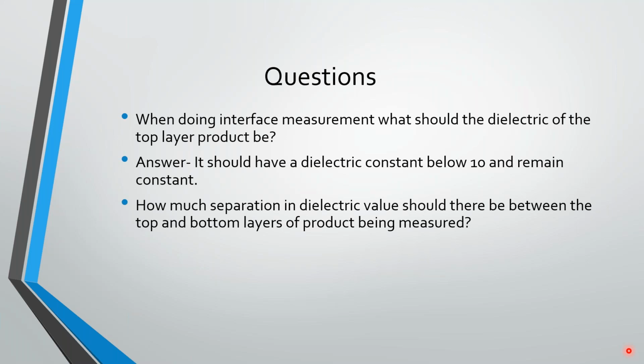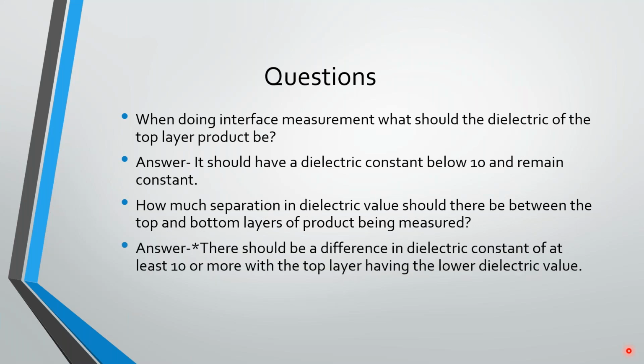How much separation in dielectric value should there be between the top and bottom layers of the products being measured? Again, it's 10 - there should be a difference in dielectric constant of at least 10. So if the top layer is 5, we'd want the bottom layer to be at least 15 or better.